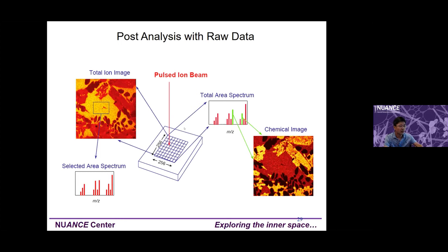This slide shows that you can collect raw data from a certain area — for example 400 by 400 microns — and save the full dataset. After collection, based on the raw data you can get spectra from different sub-areas, get a total ion image, select a specific 10 by 10 pixel region to extract a spectrum, or select a certain mass fragment and generate a mapping. This saves instrument time — you collect the raw data once and do post-processing analysis afterward.